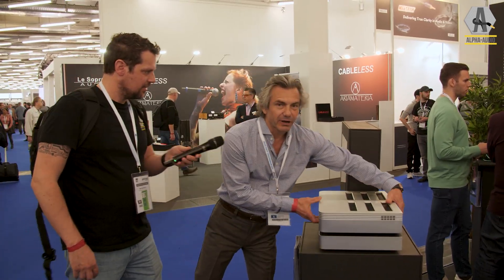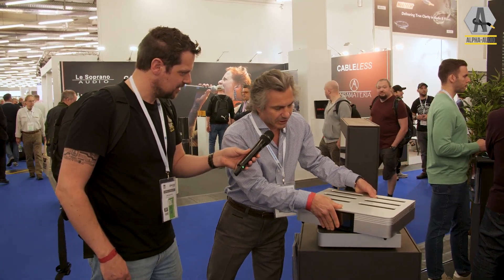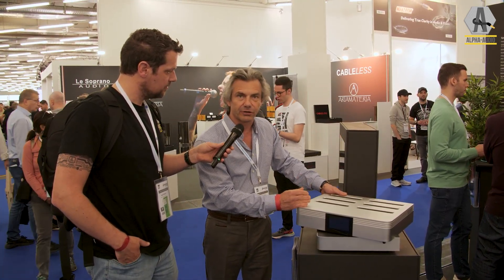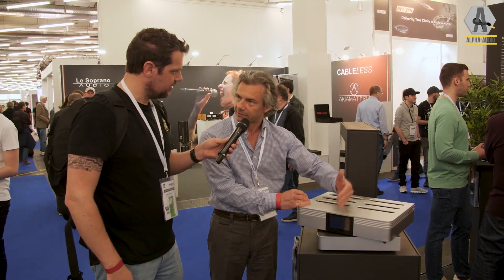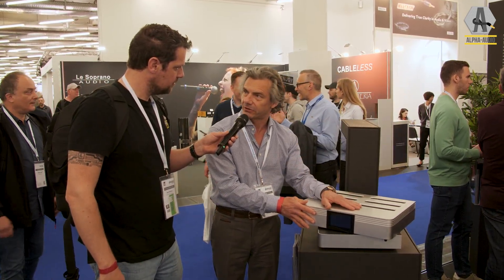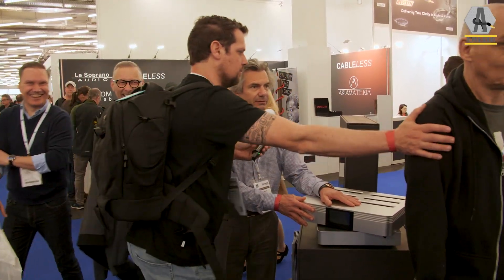We're back — I'll turn this around ever so slightly. So this is our new Centuri. It's a voltage stabilization system. It will correct the voltage from 207 back up to 230, or from 253 back down to 230. If the voltage goes outside those ranges, it will do a controlled shutdown to protect your equipment. It delivers 16 amps and will continually deliver high quality power.